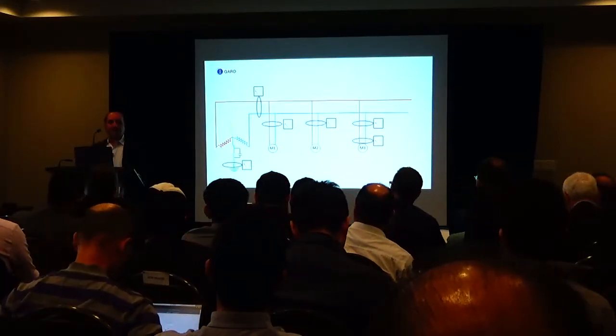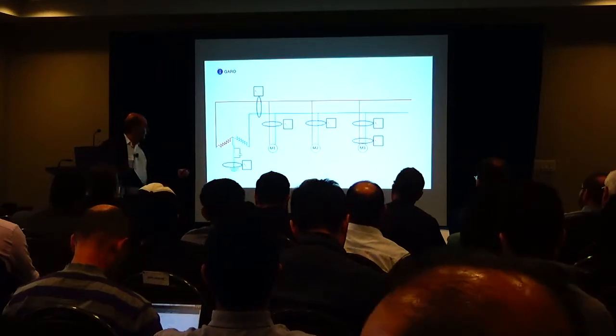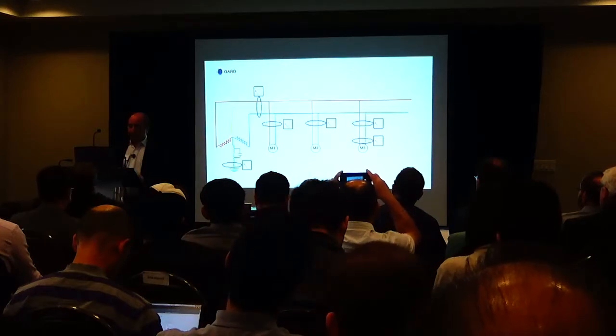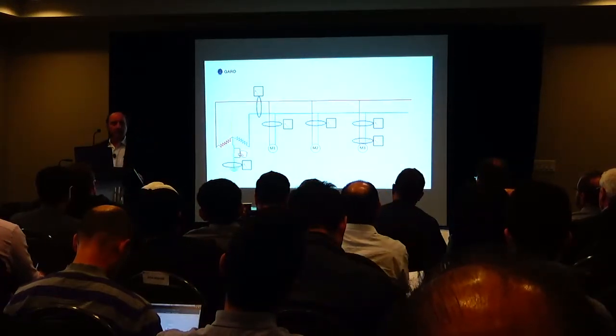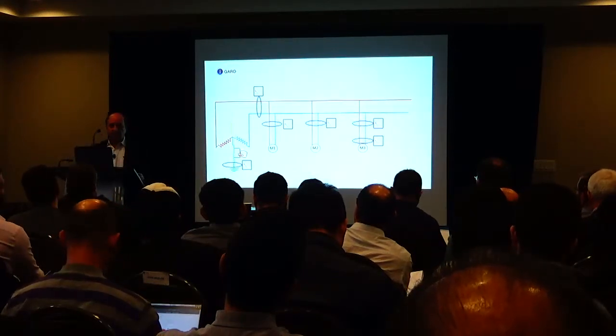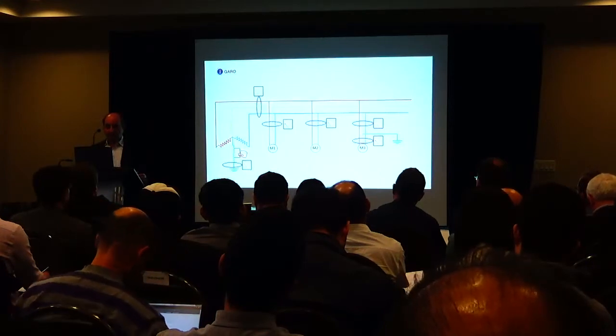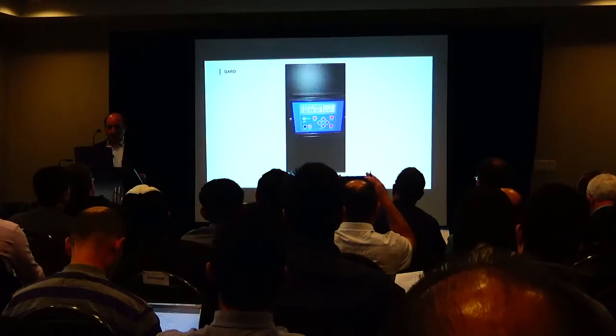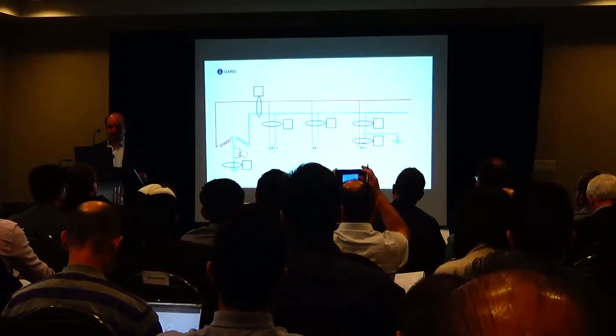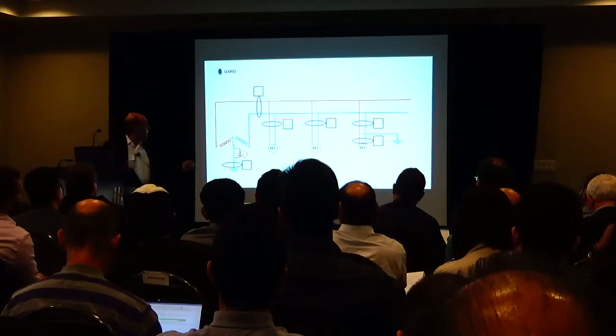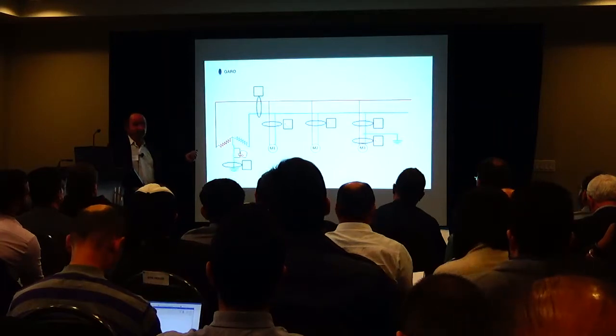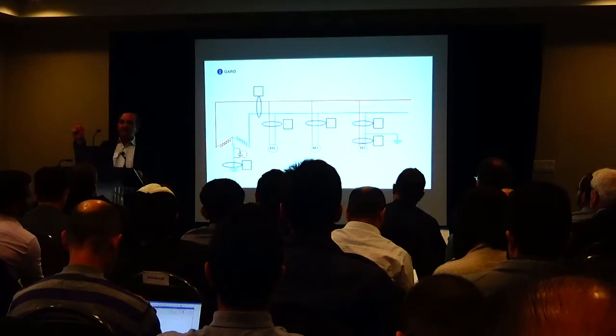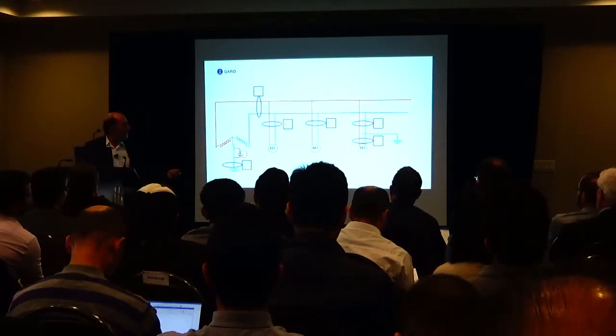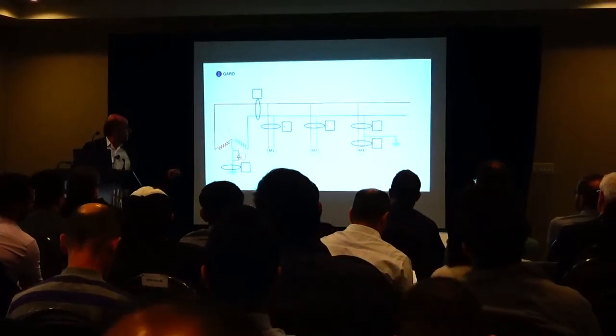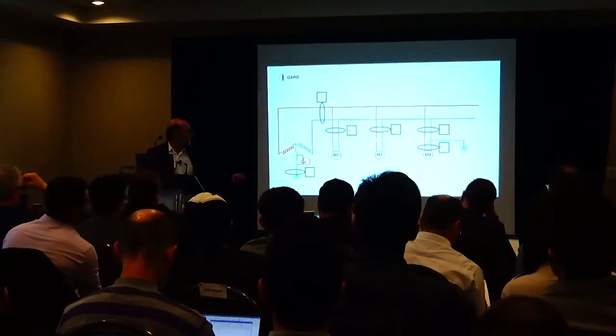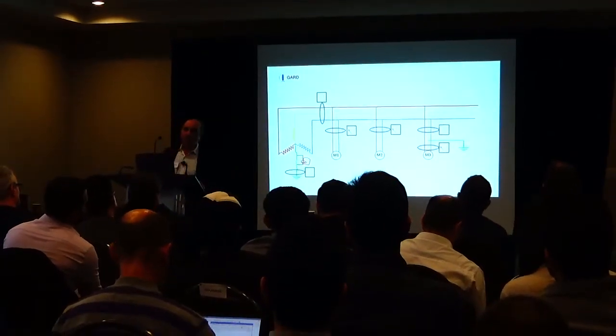But the best part of having a resistance grounded system is that now you're able to locate where the fault is. We do that by changing the value of the resistor with this contactor. So 1 second it's open, 1 second it's closed, second it's open, second it's closed. We can actually go around, and when you have a fault on the system, if you had a zero sequence CT over here, you're seeing a change. This is what Ajit was talking about. You see a change in current. Over here you see the change in current. Over here you see the change in current. You don't see it here because there's no fault down here. You don't see it here because there's no fault down here. And once you pass the point of the fault, you don't see that change in current anymore.